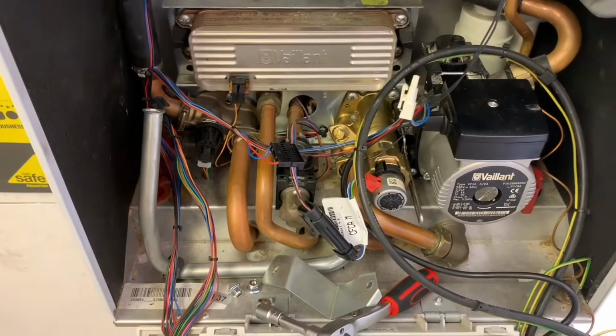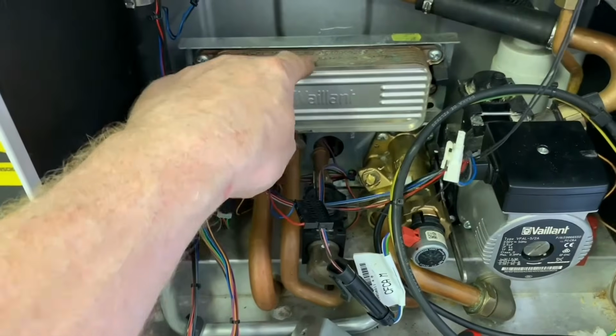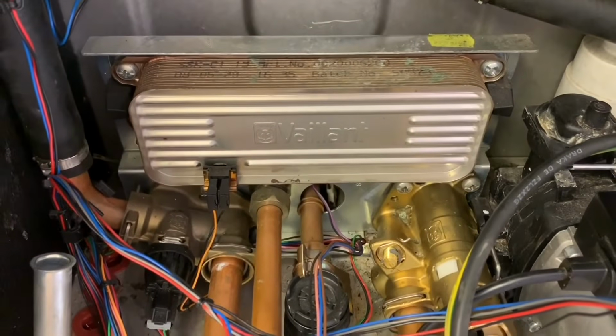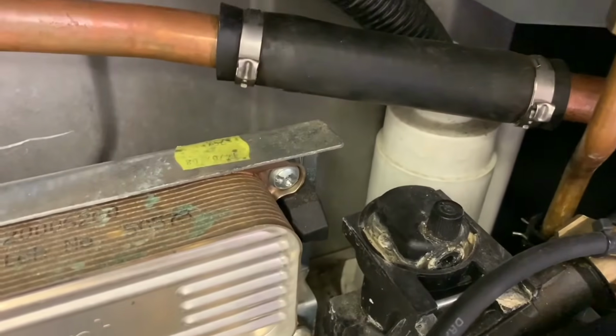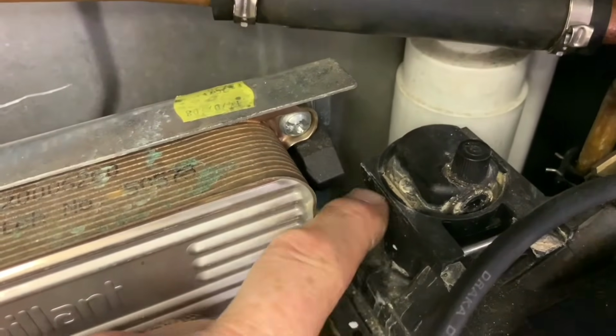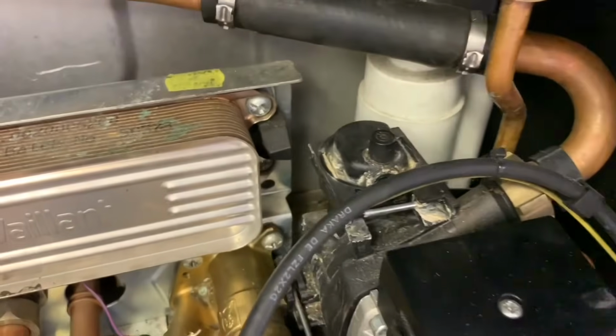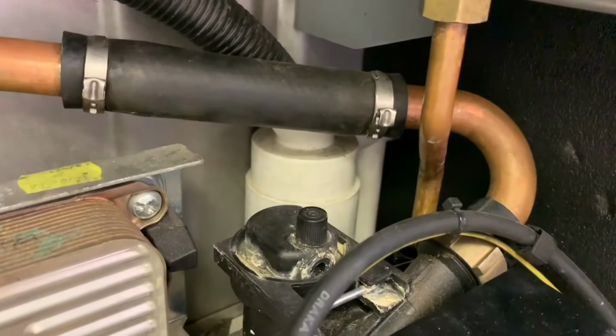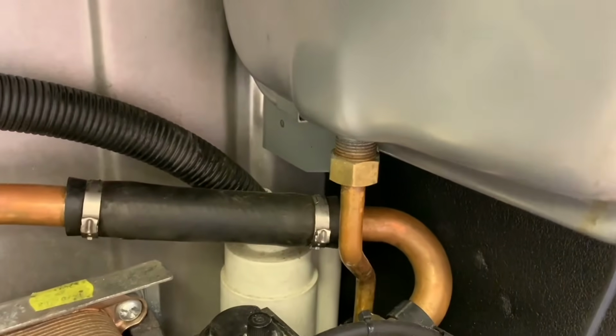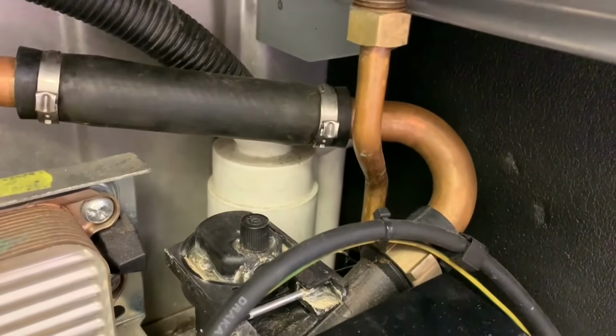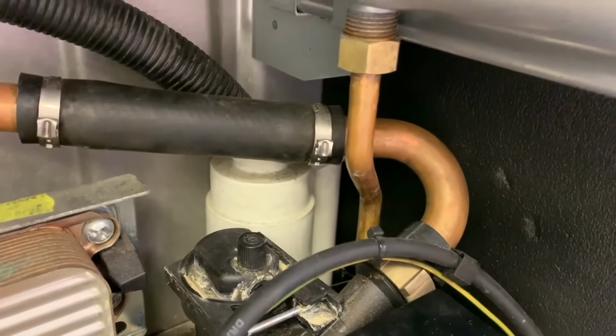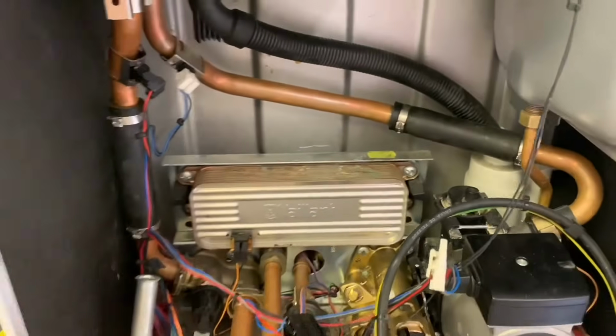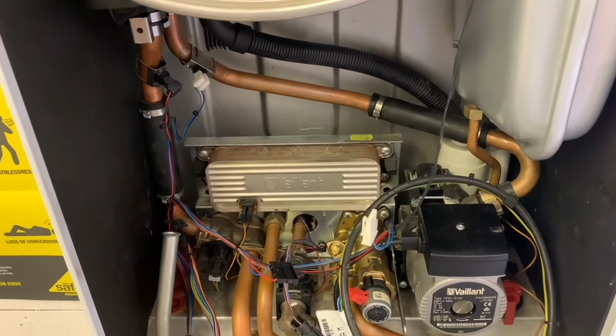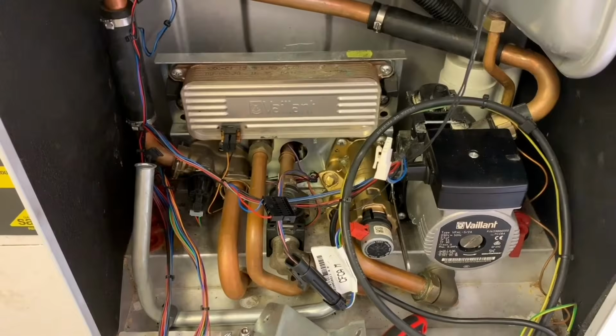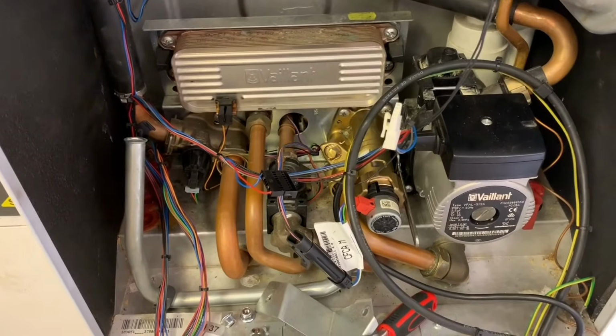And you can now see this water set a lot more closely and you can see the plate to plate better now. Okay. So right in the corner there is the actual trap and you can see how much that's been leaking as well. So this would have been on a really dirty system. And you can see our copper pipe now, which is going up to our expansion vessel. These can also be a pain in quite a few boilers. If they're a flexible hose, they get blocked up as well. So flexible hoses aren't very good inside boilers because we like to put brand new boilers on 30-year-old systems full of muck. So that's another tour around.